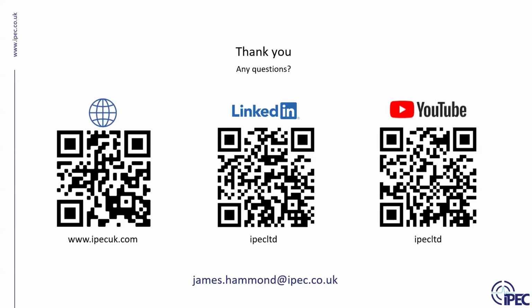Once we experienced the first failure, okay, that's a one-off. Second failure, okay, that's the start of a pattern. Once it got to the third one, it was, okay, we need to figure this thing out. So partial discharge was able to determine which ones were in greatest need of immediate replacement, and then you could schedule downtime. Same thing happened up in North Dakota.